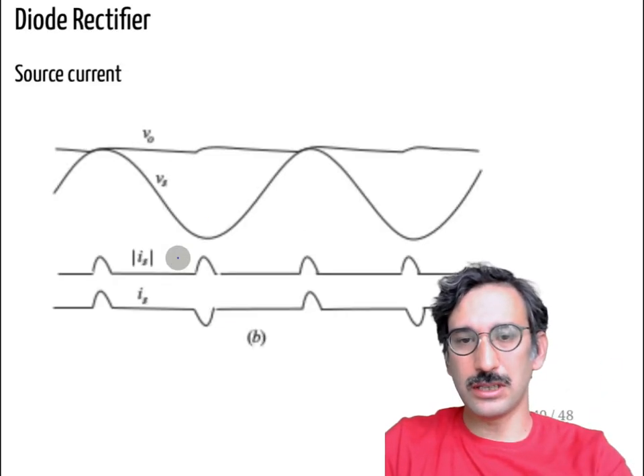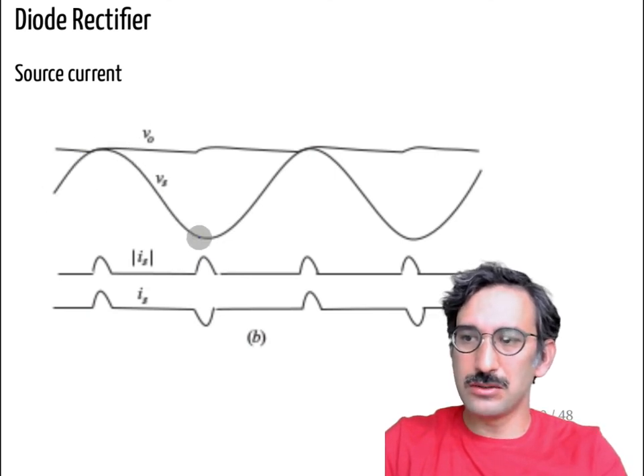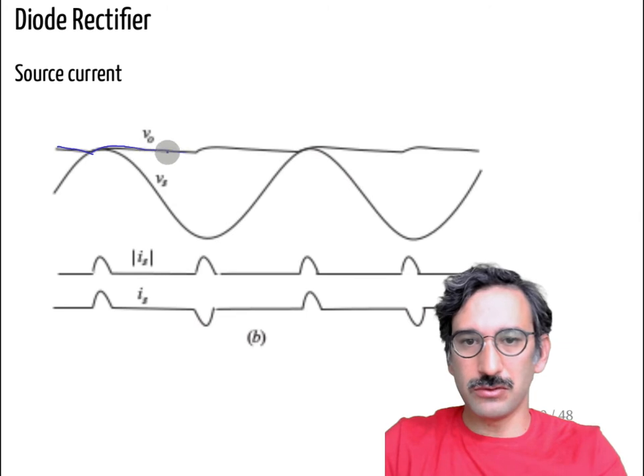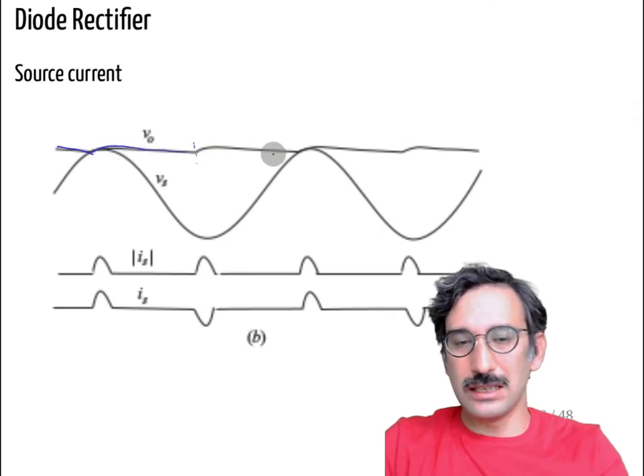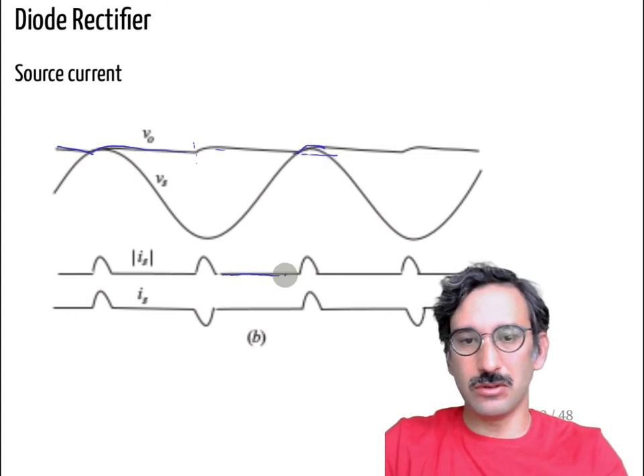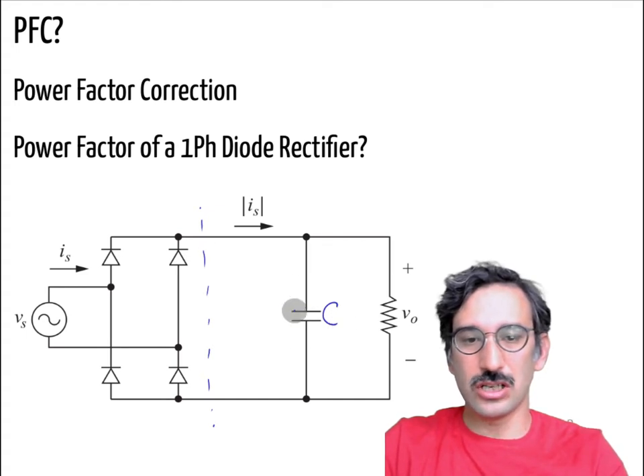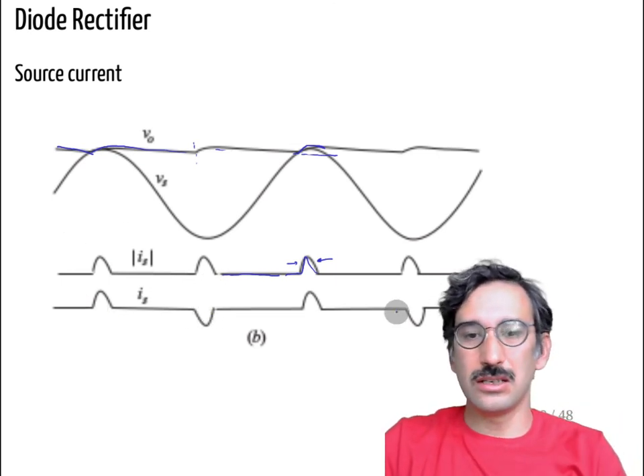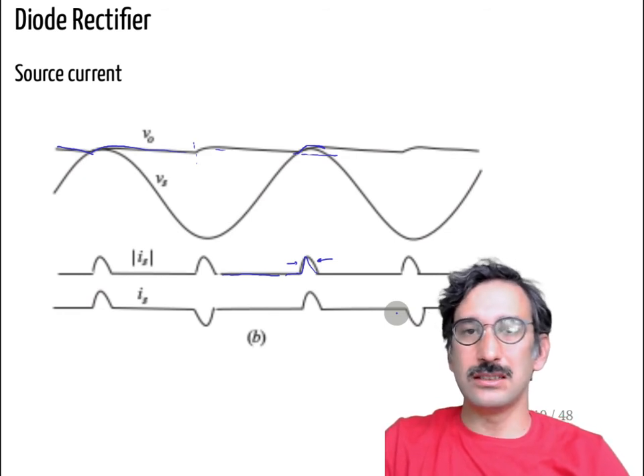Let's have a look at the waveforms. This is your source voltage and this is your capacitor voltage. Whenever your capacitor voltage is slowly decaying depending on your load, whenever it is less than the source voltage you are not drawing any current — this is your source current. Whenever your voltage tries to climb over that capacitor voltage, it draws a really short period of current, and during that time the current charges the capacitor. So at the end of the day, instead of a nice sinusoidal current you have a really peaky input current.